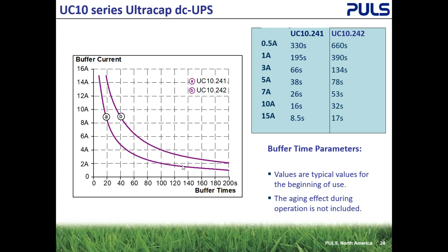Most people only need less than 2 amps to do a PLC backup. It has more than enough runtime to back up if you're running a PC. Windows 10 takes about 70 seconds to back up and draws about an amp and a half, so you've got plenty of time to do a backup on a Windows-based system or a PLC. The chart to the right shows you the runtimes.